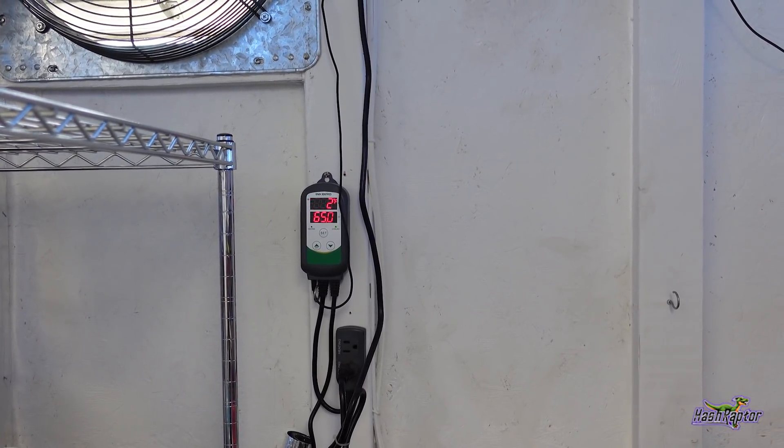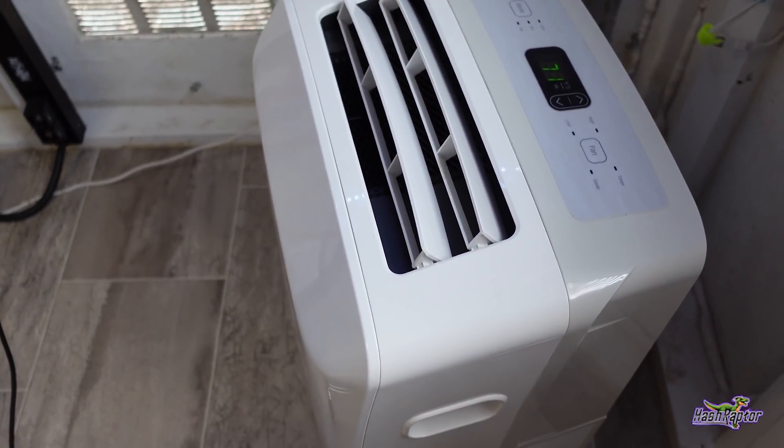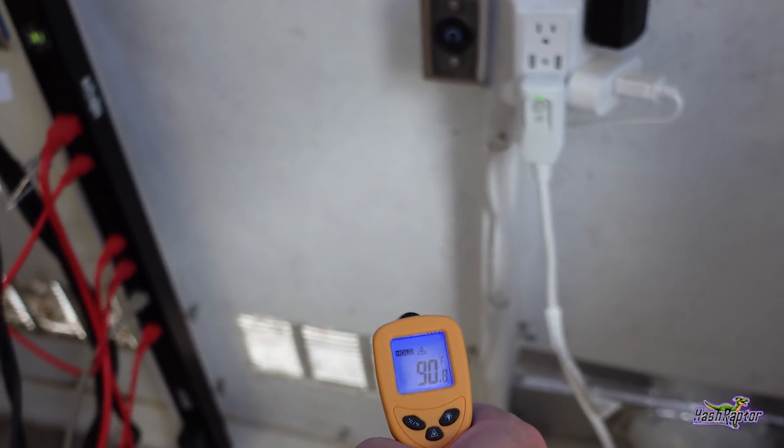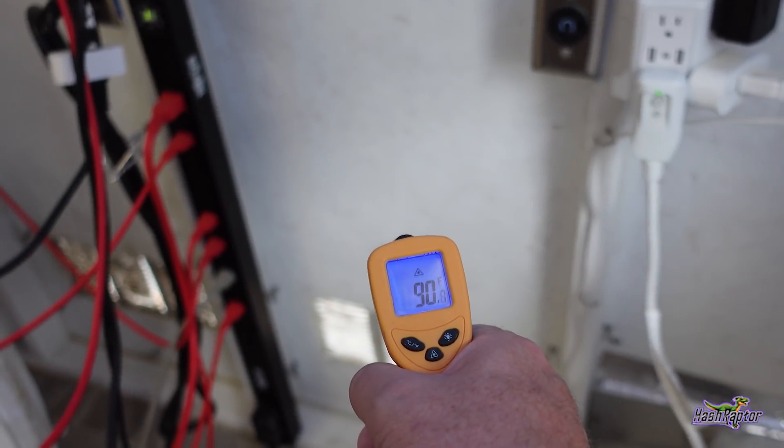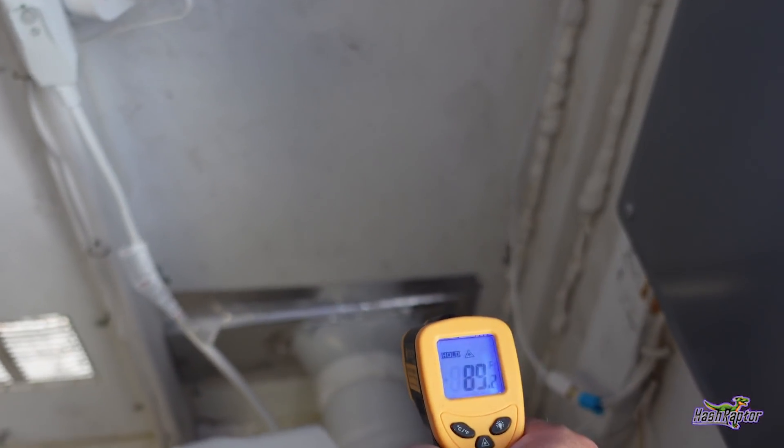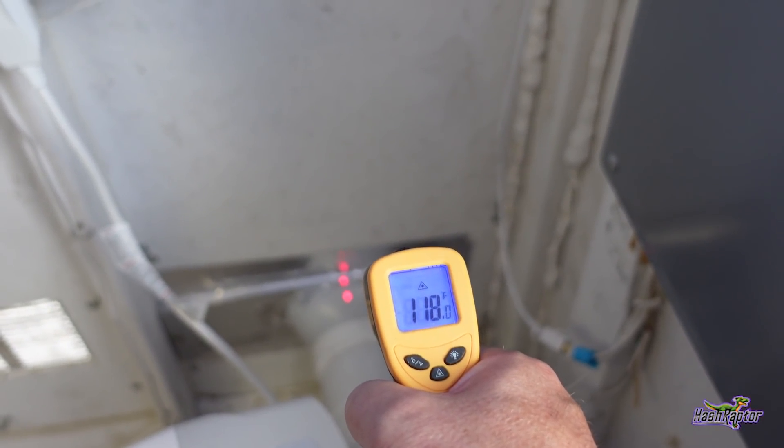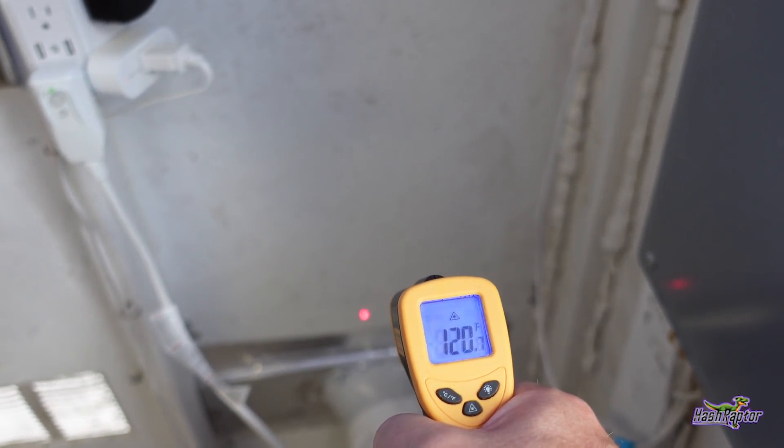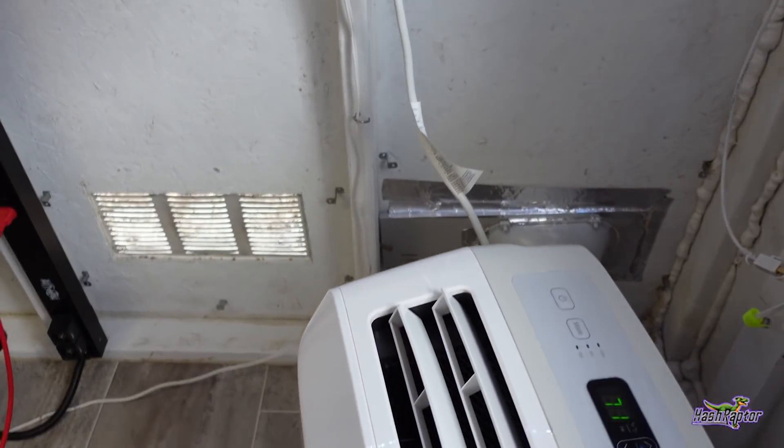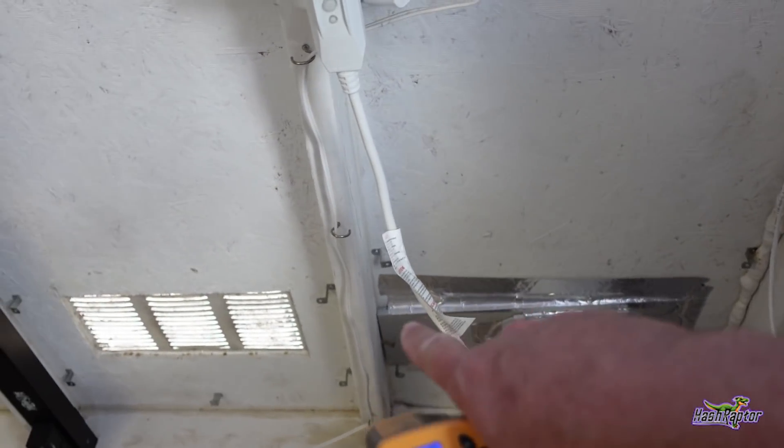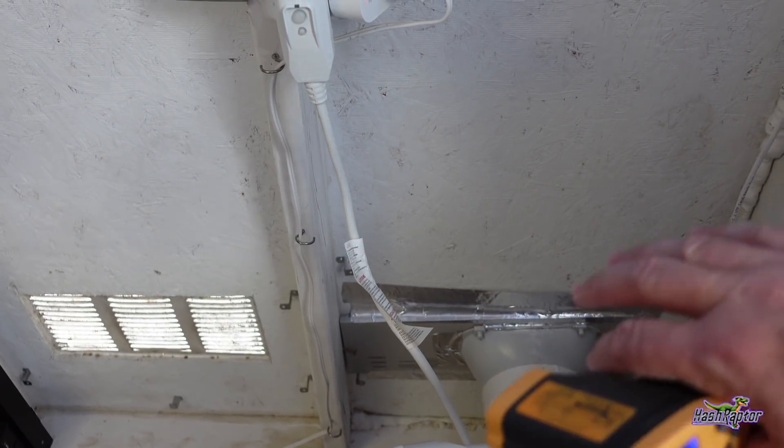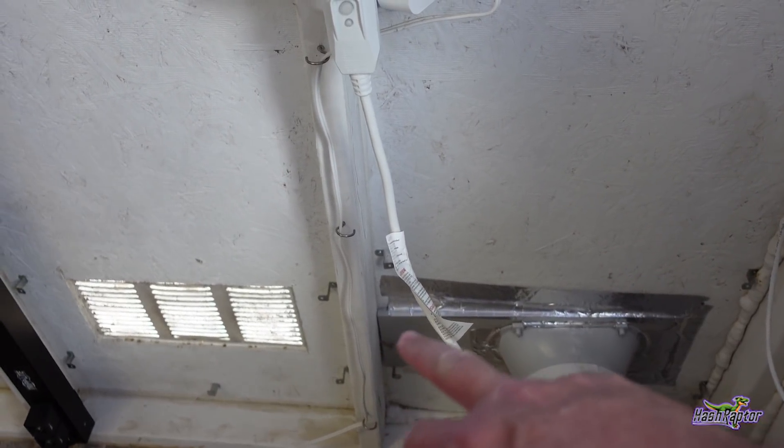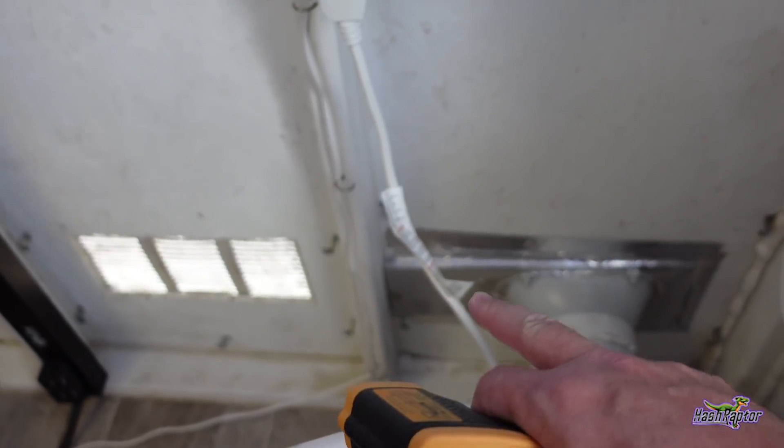Hey, I just wanted to show you this real quick beside this air conditioning unit. This is what I was mentioning when I did a touch test on this wall right here. So here we're going to shoot the wall beside this and it's what, 89, 90 degrees Fahrenheit? Check this out: 118 degrees at the exhaust. If I come up the wall, 120, 121—I mean it's hot, folks. And if I use this permanently, which again I don't know that I will, I'm going to have to find a way to really get this exhaust installed properly and exhausting away from the shed, because at the moment there's a little crack over here from where this frame doesn't fit exactly, and you can feel some heat building up in this corner.